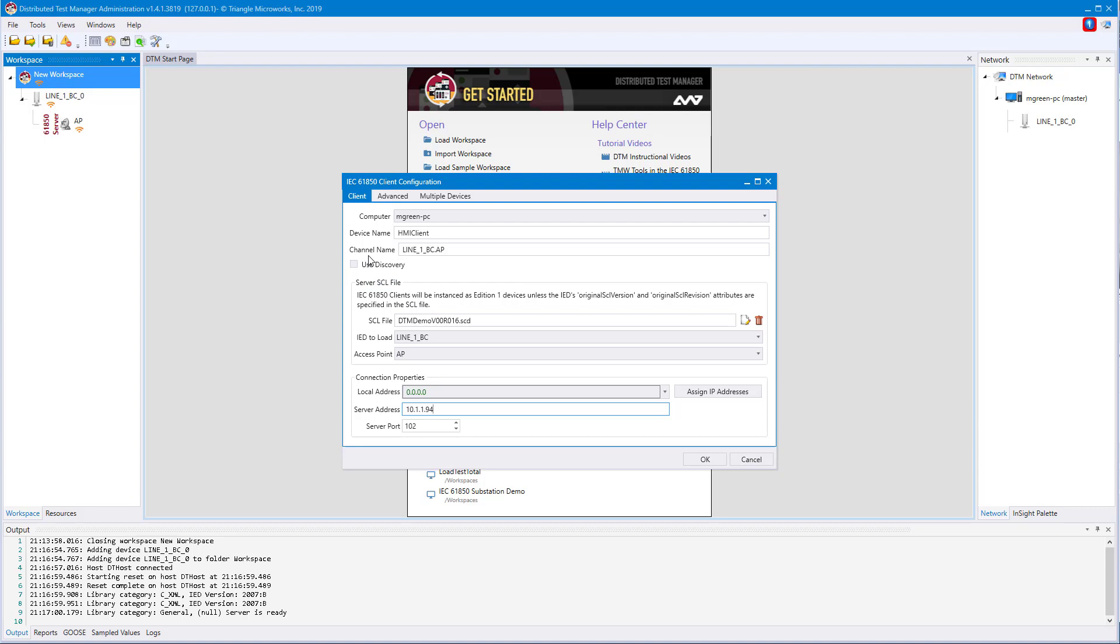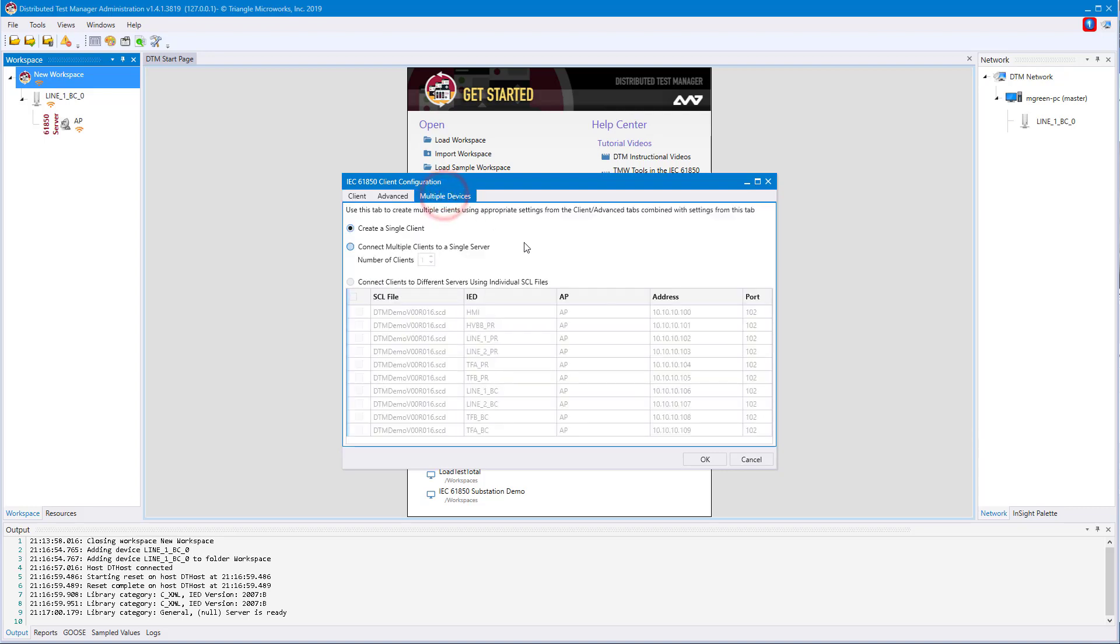If we were to create multiple IEC 61850 clients, you could go to the multiple device tab. This is slightly different than what we've seen before. In IEC 61850, you can create multiple clients to connect to one server, or you can create a client based on a server configuration found in the imported SCL files.